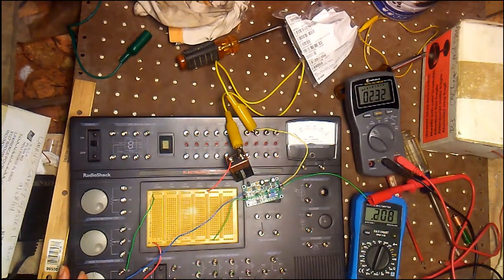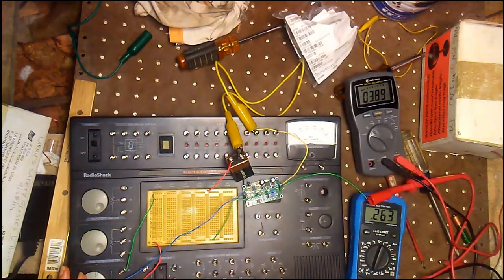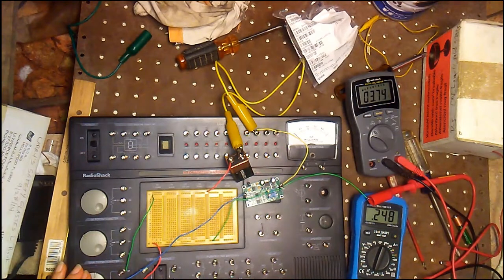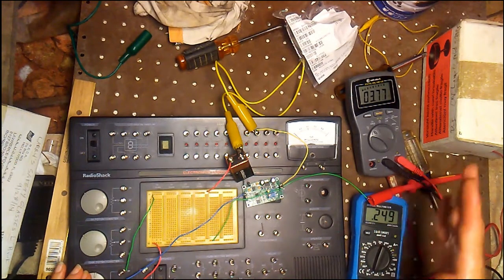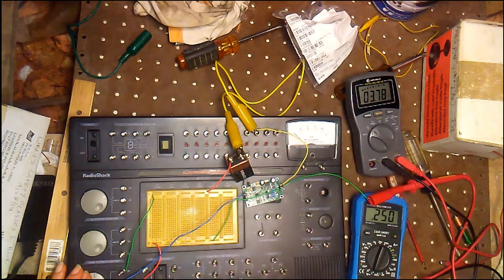If we go to 0.25, that should be 2.7 plus 1.35, or 4.05, right? Oh, so it seems we're really losing some linearity here - it should be 4.05, and it's only 3.78. If we go up to 0.3, that should be 5.4, and instead it's only 4.09. Of course, this is at the limit of the input of this module.